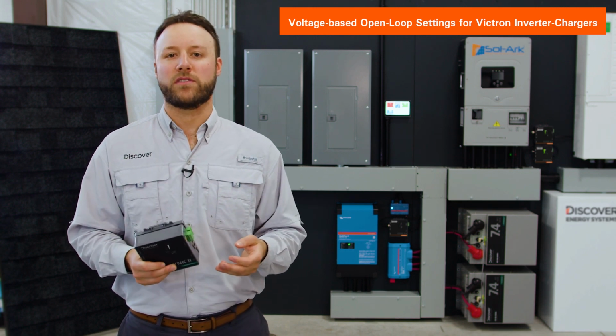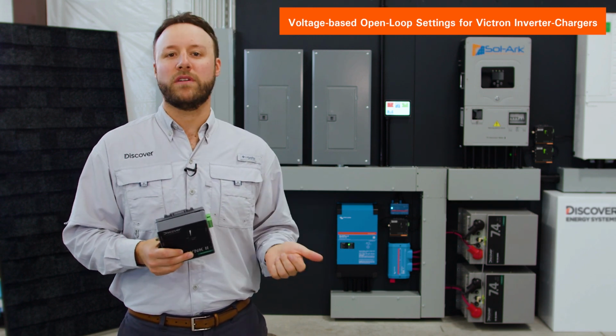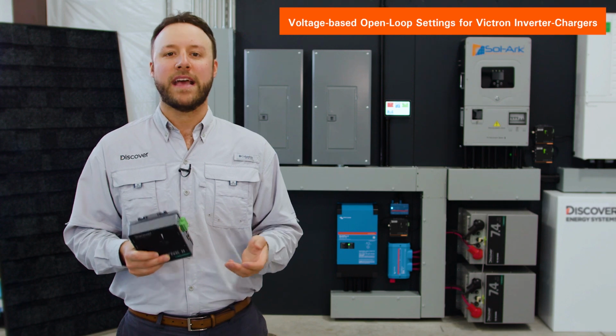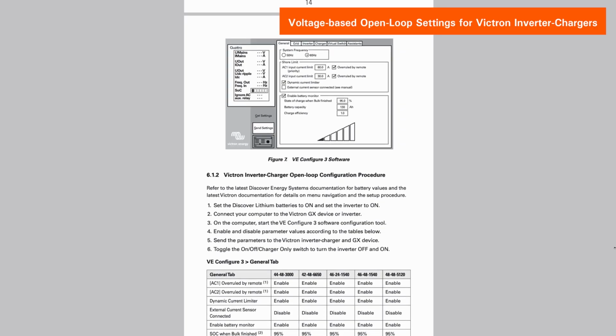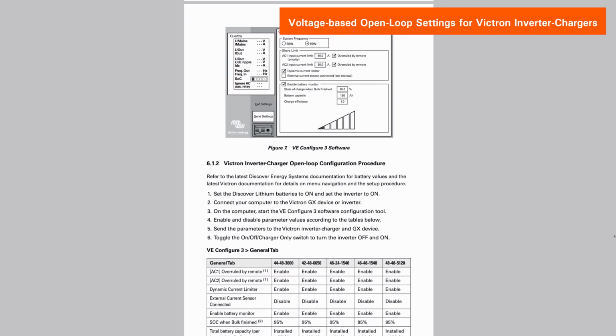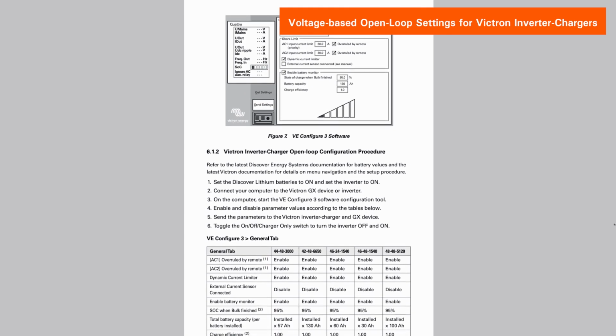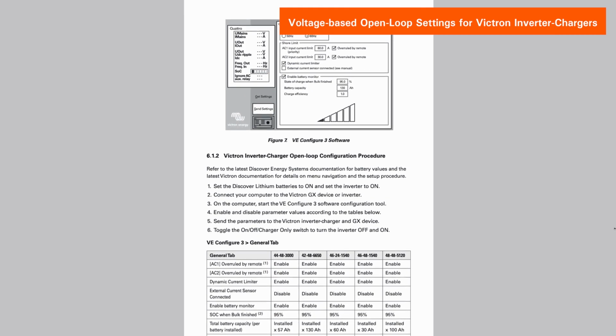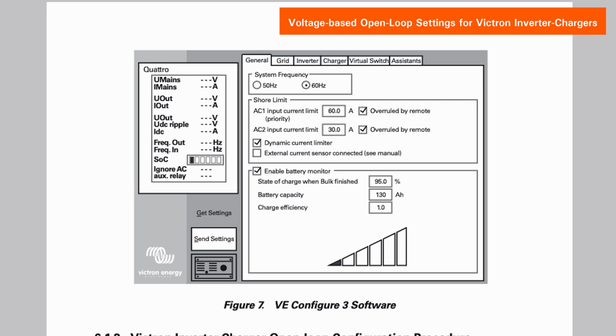Using the VE Configure software, navigate to each general inverter and charger tab and set the parameters. For more guidance on these settings, refer to section 6.1 of the LYNK II Victron user manual. After setting the open loop parameters, save all the parameters to the inverter charger and the GX device by clicking on the Send Settings button. Restart the GX device after completion.